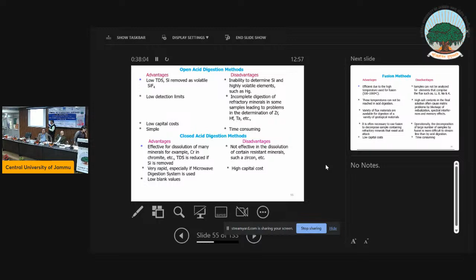The disadvantage of open acid digestion is that, because you are using HF, HCl, HClO4, refractory phases will not break down. They will not come into solution, and it is time consuming, cost is low, and pollution also takes place, compared to micro closed digestion, where TDS is reduced. If silica is removed, like people are using boric acid and then removing it. Otherwise, in a closed vessel, nothing is going out, no evaporation. So if you want to take it out, you have to do it after digestion, chemically. But cost is there, it is rapid, etc., low blanks.